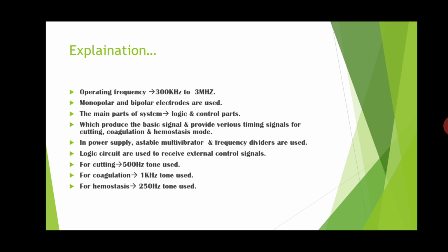For coagulation, they are using a 1 kilohertz tone. During the cutting process, they are using a 500 hertz tone. And for hemostasis, the tone is 250 hertz.